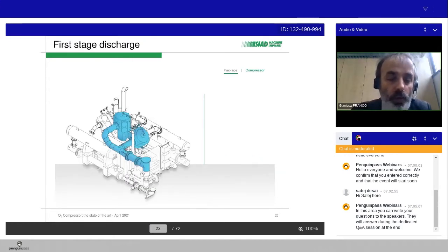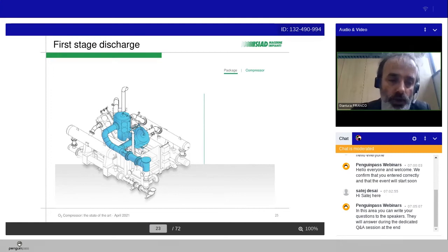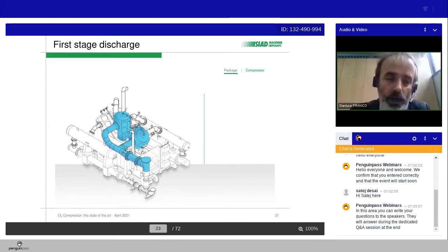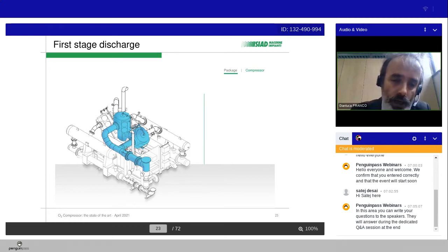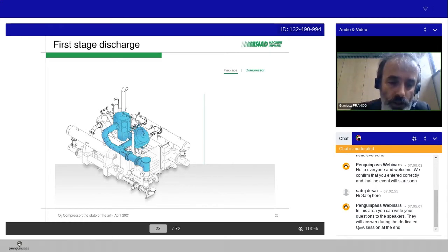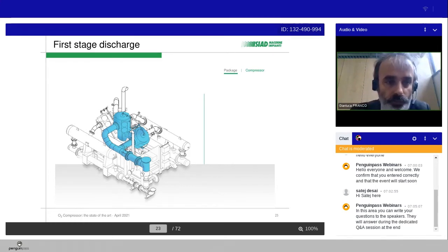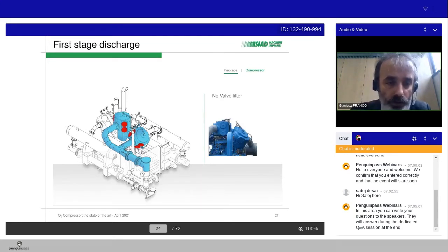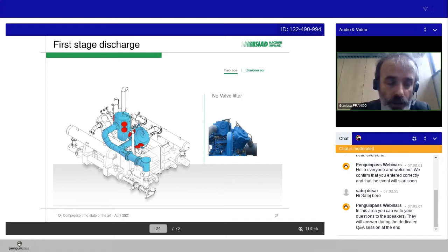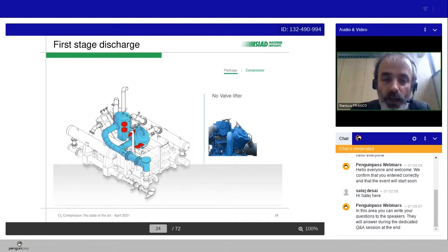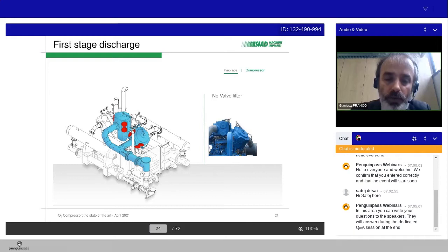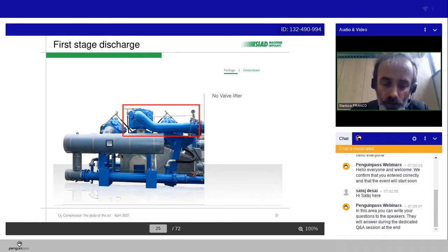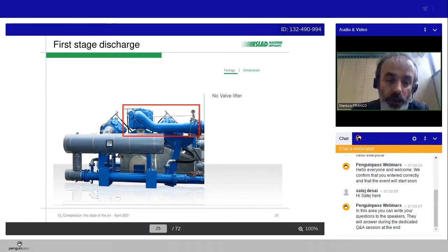Then we have the first stage suction. In this case, for this compressor, we have two cylinders in parallel with the common suction line and the discharge line. Here we have the valves, and we underline that we don't have for oxygen compressor the valve lifter. It means that you can regulate the flow in a different way.